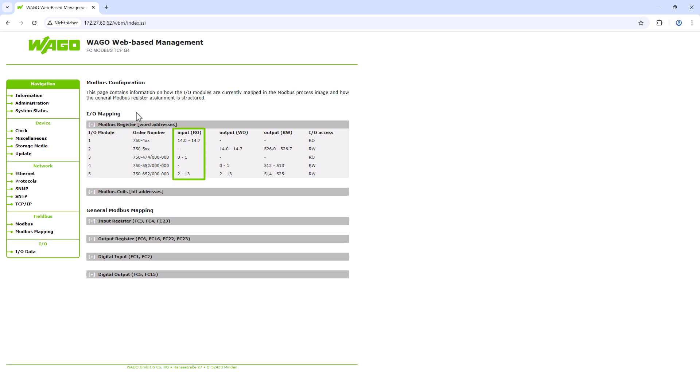This column lists the input addresses that are the Modbus word addresses. We also see here that the addresses of the digital inputs are always appended after the other modules, regardless of their position. The next column lists the addresses of the outputs.